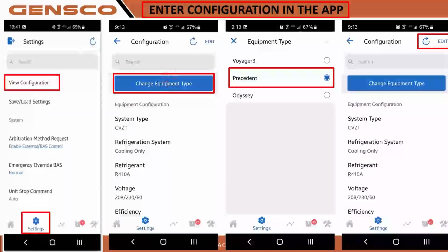change equipment type. Now, if we're replacing the board, this board can be set up for an Odyssey split, Precedent package, or the larger Voyager 3. Again, if we're using it in Precedent, we got to make sure we're choosing Precedent. These are older slides, so watch for this. If it says 410A, we'll have to change that to our 454B. So if it thinks we're on 410A, we're not going to be looking for the mitigation control sensor. You might have to change your voltages. Again, if you order it from factory, they should all be set up already. System type, this is for our fan, so this is constant volume zone temp. Always put it on constant volume CVZT, unless we're getting into some VAV boxes. For the larger ones, it'll be VVZT, variable volume zone temp, which could be into multi-zones.